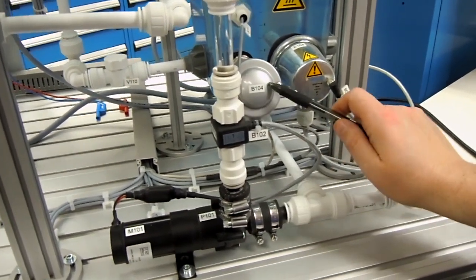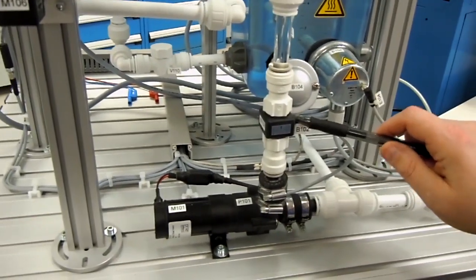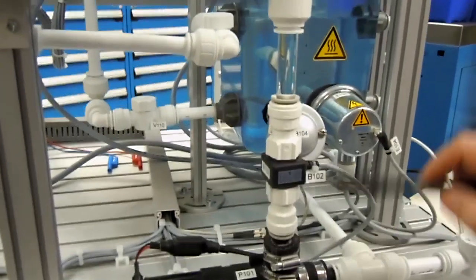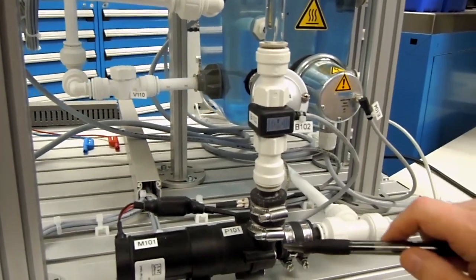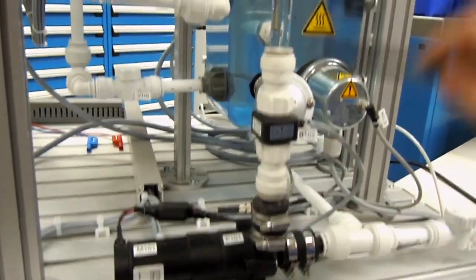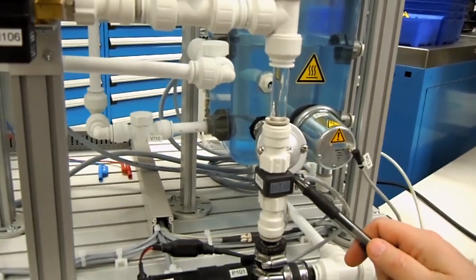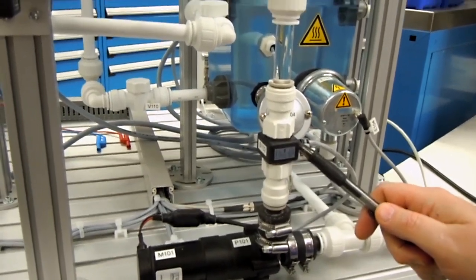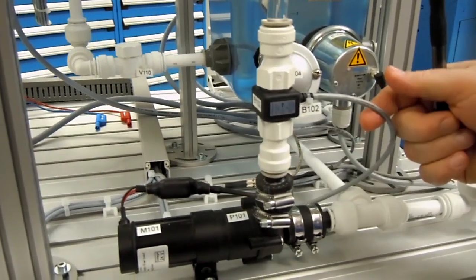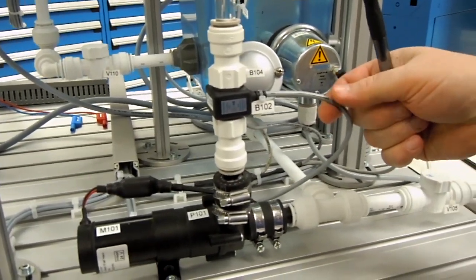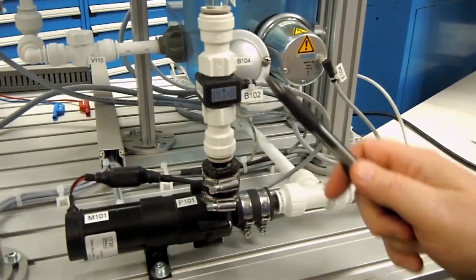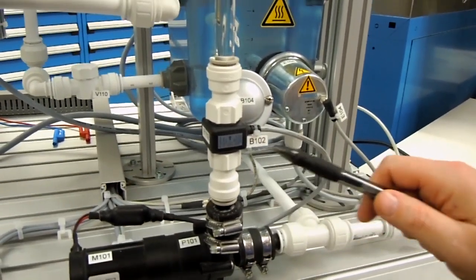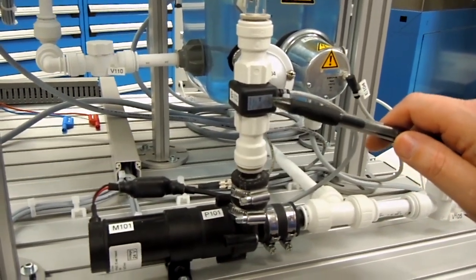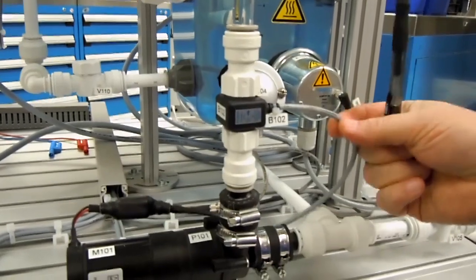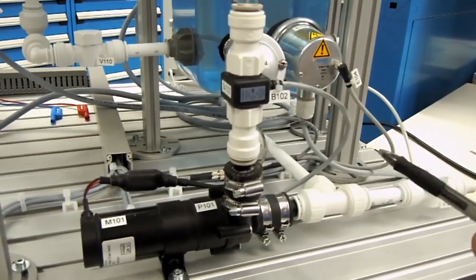It's called B104. Moving over to here, this is the flow sensor. It has water flowing through these pipes, comes through the pump motor into this tubing here, but measures a flow rate in the range of 0 to 9 liters per minute, and coming out of this cable is 0 to 1200 hertz. Okay, so it's proportional to the flow rate that you have here. Eventually I'll talk about the converter modules that are in the back, but again, 0 to 9 liters of flow coming in, 0 to 1200 pulses per second coming out. So that's the flow sensor.